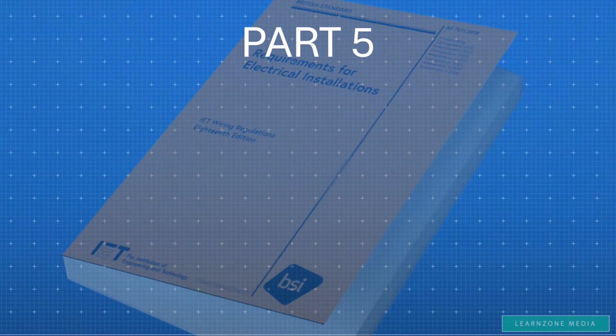Then, in Part 5, we have the introduction of the functional bonding conductor. This is another new addition to the wiring regulations, with the emphasis being on functional. So the purpose is functional, not protective. As such, it must not be confused or used as a protective conductor, and it mustn't replace the earthing or bonding required.